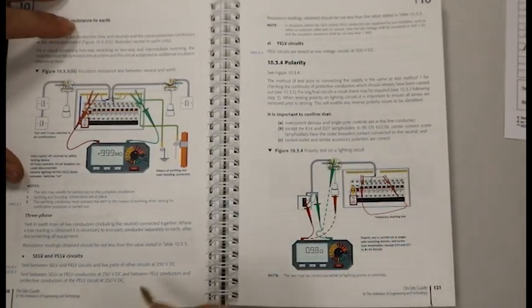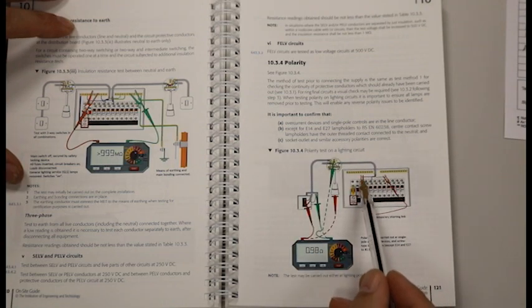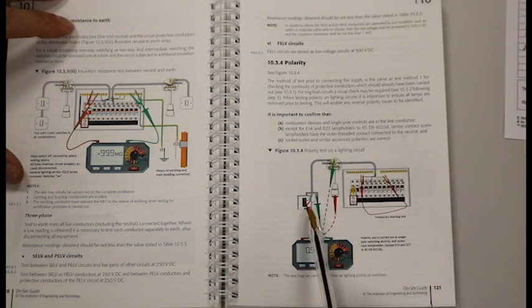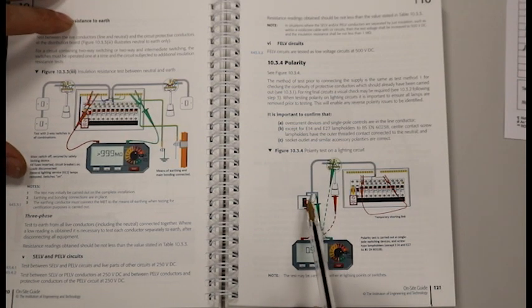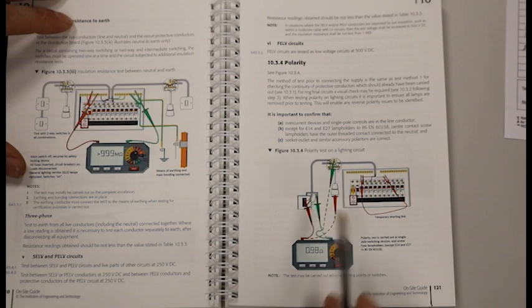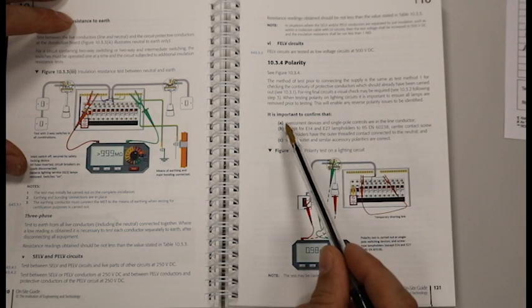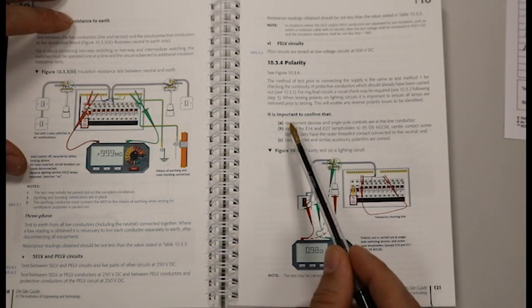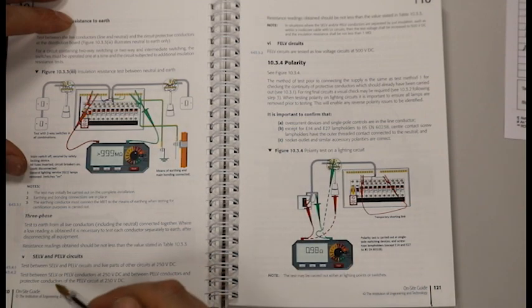Page 131, we have a picture here showing a temporary link between live and earth and then our tester is at our sockets or lighting circuits. We're testing between live and earth which is exactly the test we did for our R1 plus R2. Here we've got further details of polarity test A, B and C which I spoke about earlier on. That is our polarity test complete.